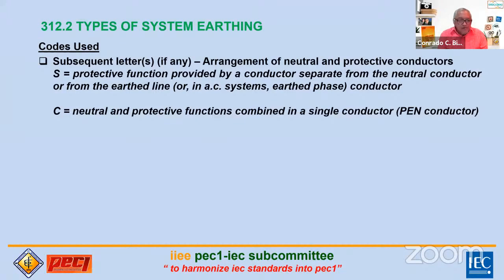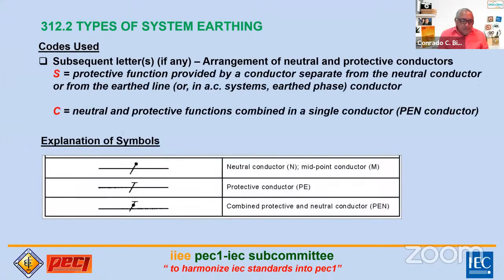Now let's look at the diagrams. We have some diagrams here - let me show you some symbols first since we'll see these in the diagrams. There's a symbol with a dot and a diagonal line - the horizontal part is the conductor, and this type of symbol represents a neutral conductor or midpoint conductor. If we see a horizontal line over what looks like a T, that's the protective conductor, PE, protective earth. If it's a combination of both, it's a combined protective and neutral conductor, PEN.